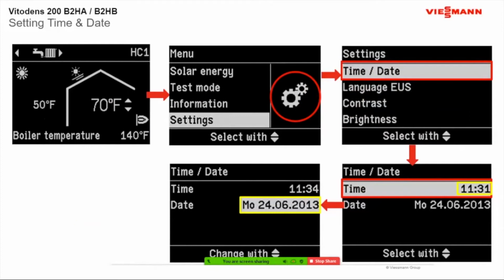Time and date. I always like to talk about the time and date and why it's important to set the time and date on this boiler. I find it very essential if you're doing time programs, domestic recirculation on and off. You can do on and off for your domestic as well as on and off with your heat program. So you can have a heating time program and a domestic time program. If you're doing the same times for heating and domestic, you can leave it in automatic. When you go to set a time program for your domestic, if you just click automatic, it will automatically follow the heat time program. If you want a separate domestic program, you put it in individual, and you'll have an individual time program for your heating and an individual time program for your domestic.